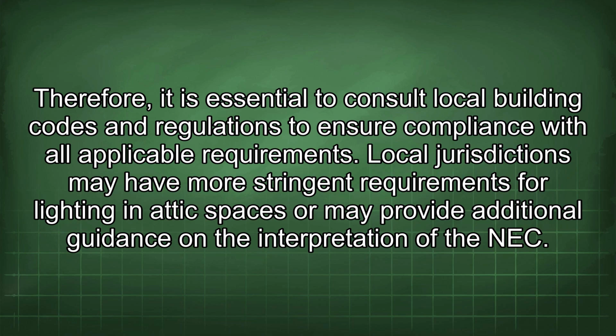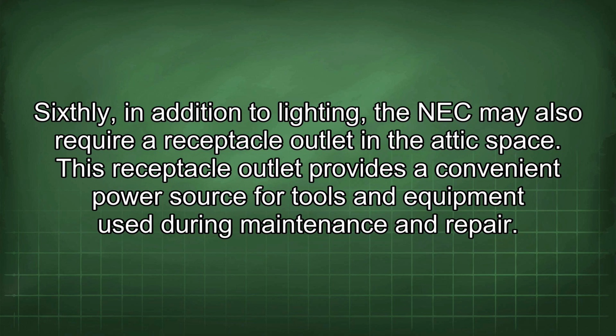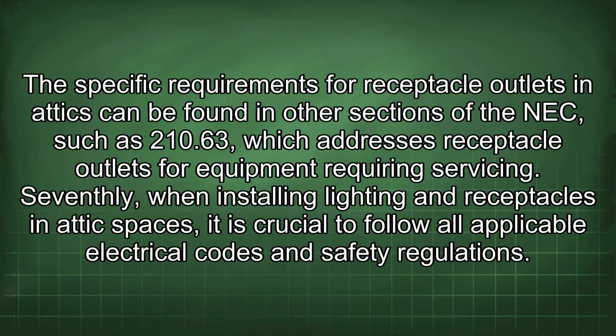of the NEC. Sixthly, in addition to lighting, the NEC may also require a receptacle outlet in the attic space. This receptacle outlet provides a convenient power source for tools and equipment used during maintenance and repair. The specific requirements for receptacle outlets in attics can be found in other sections of the NEC, such as 210.63, which addresses receptacle outlets for equipment requiring servicing.